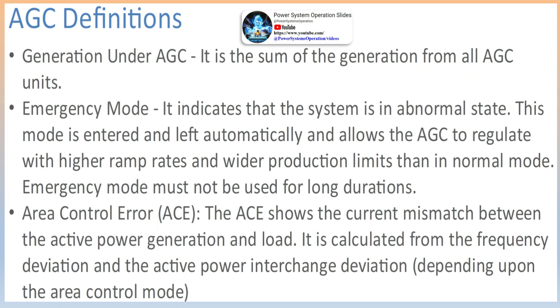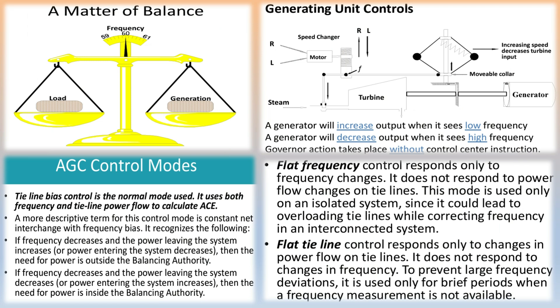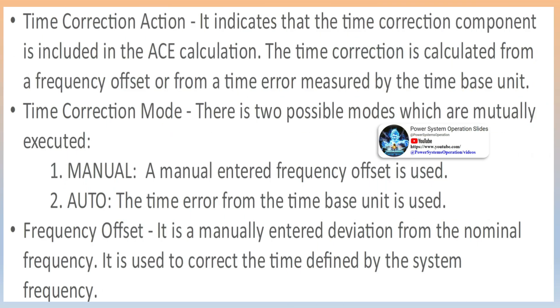AGC operating functions: if the ACE moves outside a predetermined limit, the AGC will suspend and go to monitor mode and no longer send control outputs to the AGC generators. The generation dispatcher must then control the system manually by contacting power plants to adjust the generation within control limits. Power plant and generation dispatcher interaction: the power plant operator must have units available for AGC control. The power plant operator will place the units available for AGC on remote control by a control switch located in the power plant control room. Each AGC unit will have a control switch which can be selected for local or remote control.